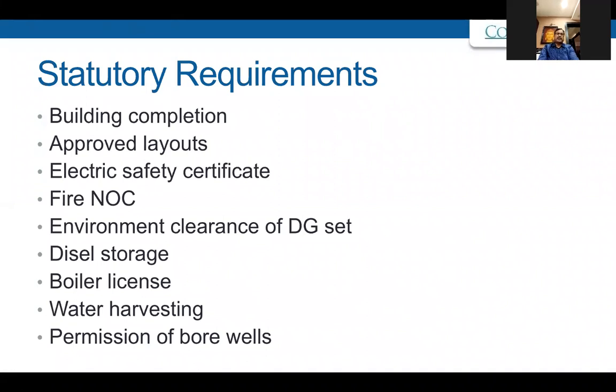But individually, in the storage tanks, you can store up to 1,000 liters. That is attached with your generator sets also. All the generator sets come with this storage capacity only, and they do not exceed this storage capacity, keeping in view the statutory requirements.